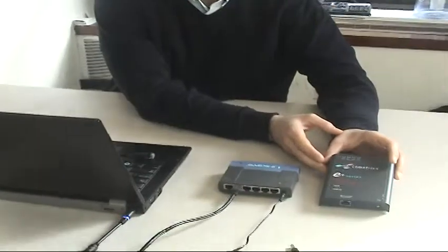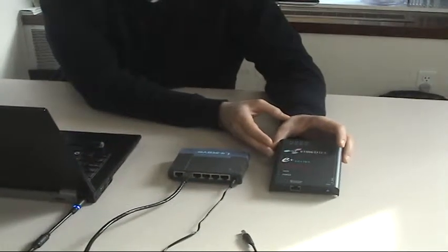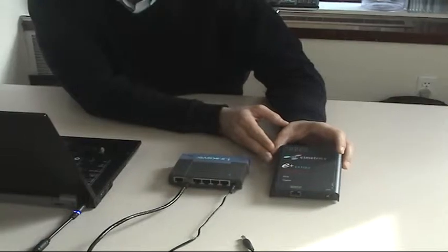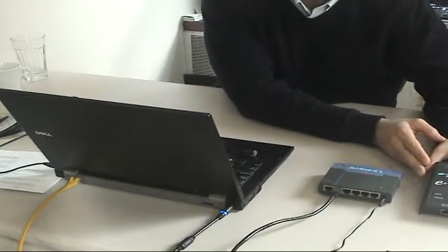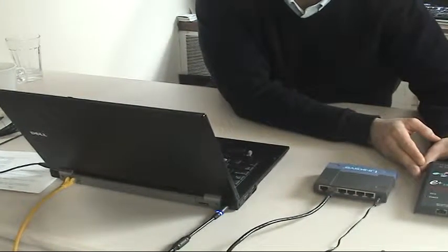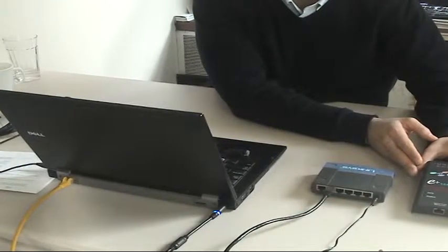Before you connect the EasyMap to the network with the meters, you first need to configure it with an IP address. It's best to put the EasyMap on a network isolated with your PC. The EasyMap comes with a default IP address, 192.168.88.89. So in order to communicate with your computer, you first need to configure your computer to IP address 192.168.88.90 with a subnet mask of 255.255.255.252, as explained in the documentation that comes with the EasyMap.